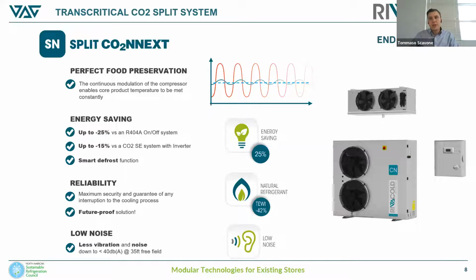The same modulation, together with other highly efficient components in the system, bring important energy savings to the end user, up to 25% compared to an on-off R404A system, and 15% against a CO2 system with semi-hermetic compressors plus inverter. The circuit has been integrated with several safety components and important alarms and controls to ensure the cooling process doesn't ever interrupt, and guaranteeing that way high reliability to the customer.